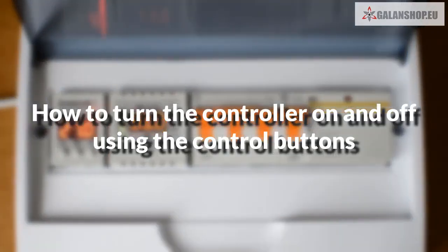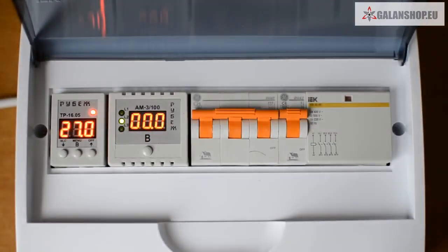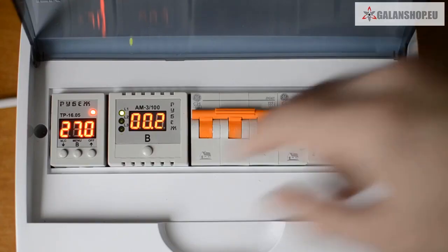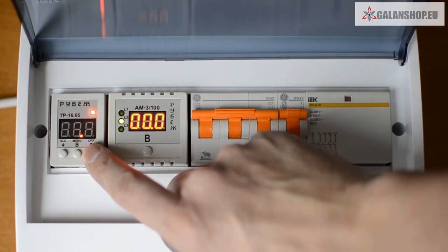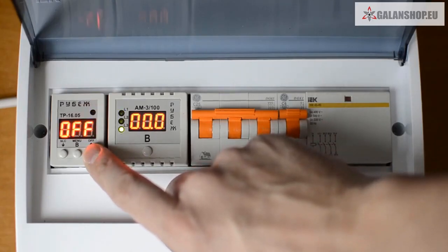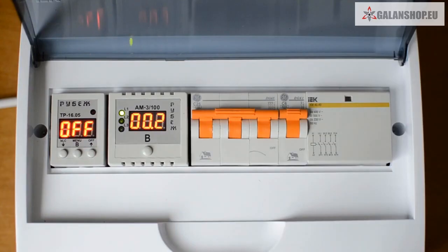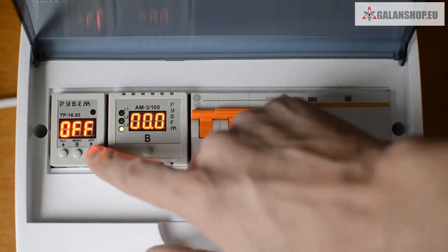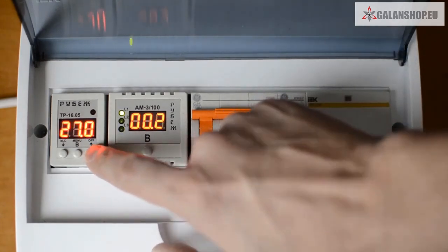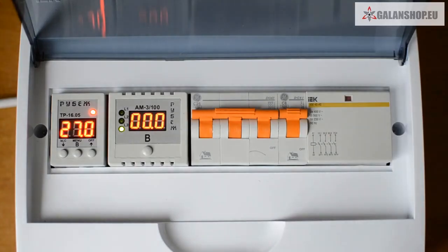How to turn the controller on and off using the control buttons. In order to switch the controller off, use the up arrow button. To do it, you need to press and hold it for around 4 seconds. When you see OFF, the controller is off, and the boiler is off. In the same way, you can switch the controller on. In this case, you hold the same button for around 2 seconds. Here you see the current temperature and the little red light, thus the boiler is on. This is how the TR16 heating controller works.